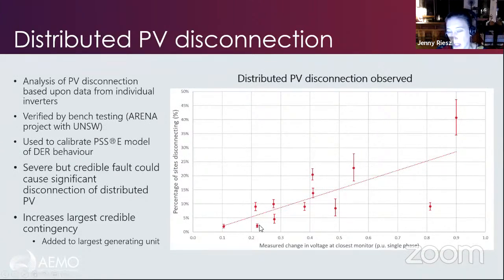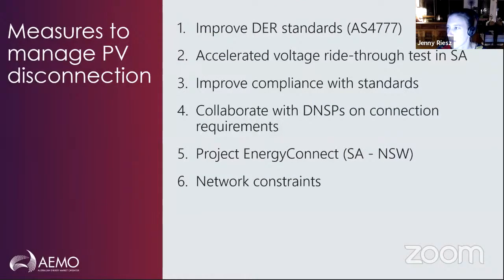We've now built some power system models that represent this behavior so that we can study what it means for power system security. And what we found is that if we have a severe fault in certain locations on our grid, that could cause a very significant amount of distributed PV to disconnect. And that can increase the contingency sizes that we need to manage. So we normally have enough frequency reserve to manage the loss of the largest unit. We now need to manage the loss of the largest unit plus an amount of distributed PV that may disconnect in that disturbance as well. So it's increasing our frequency reserves at certain times.